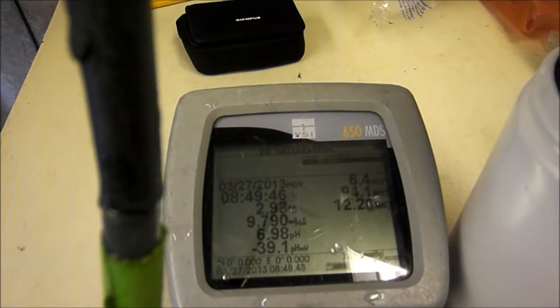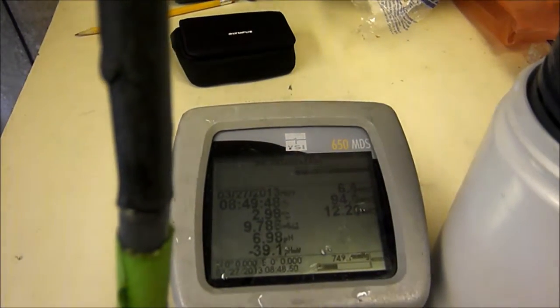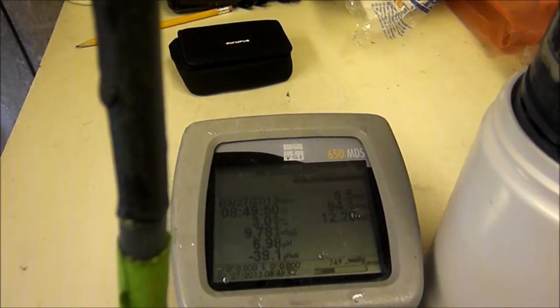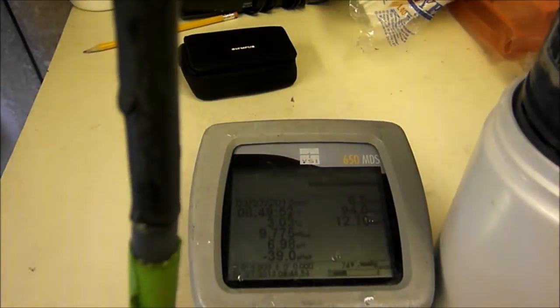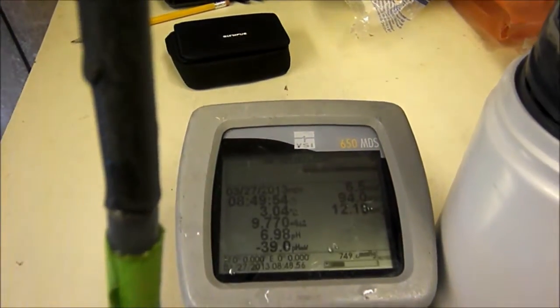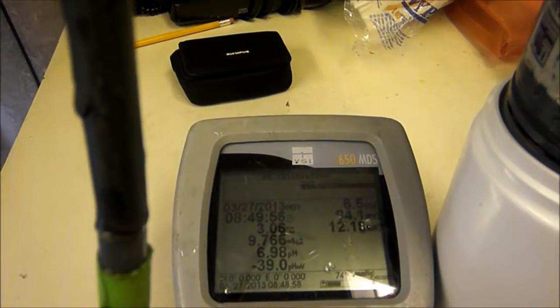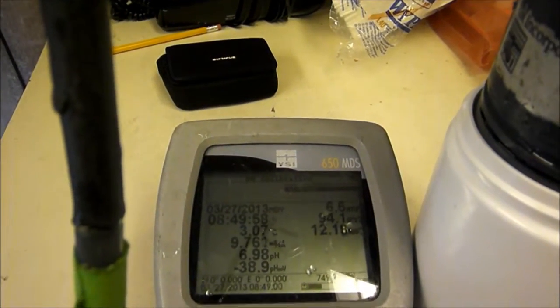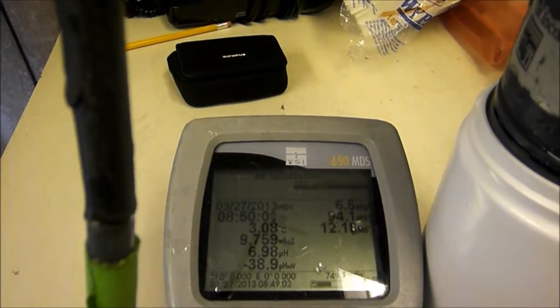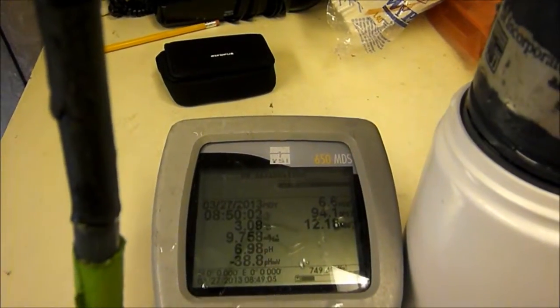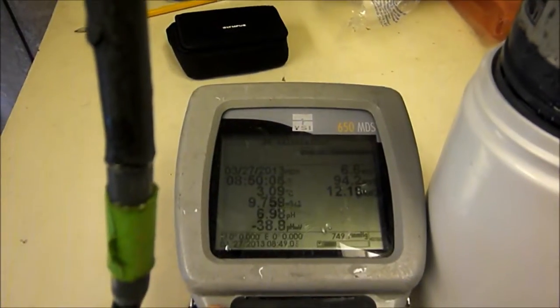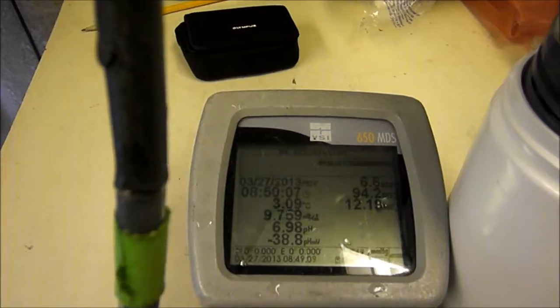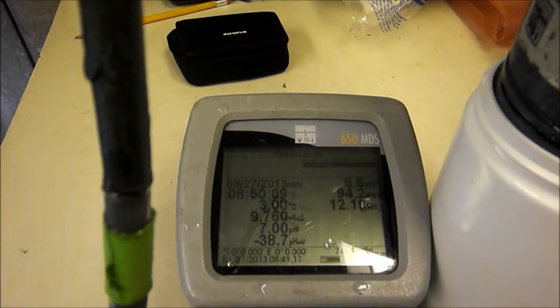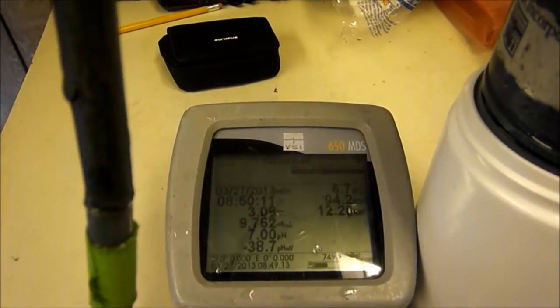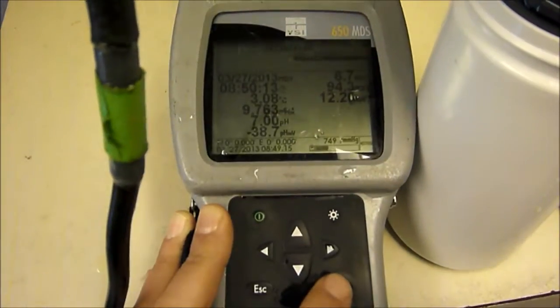So right now we're at about 6.98 on a pH 7 solution. Usually it takes between 30 seconds and 90 seconds to equilibrate. Sometimes I'll let it go a little longer just to make sure, but looks pretty steady at 6.98. And I'm going to just go ahead and hit calibrate, and there it's at 7, and then hit enter and continue.